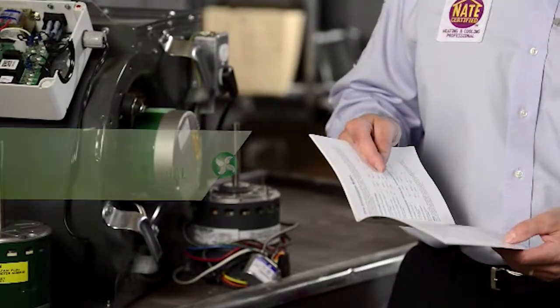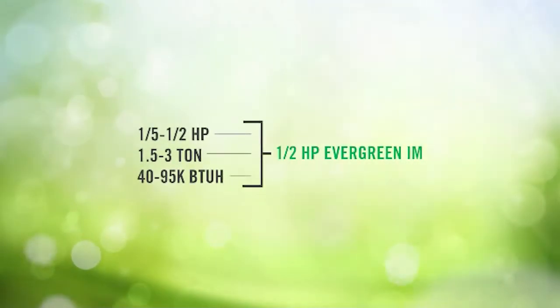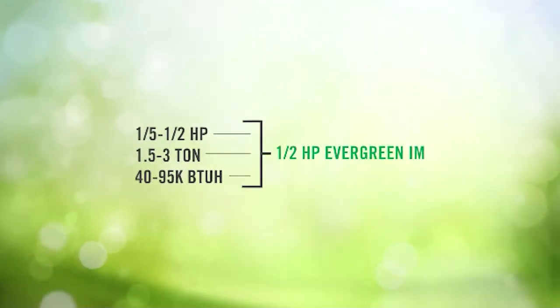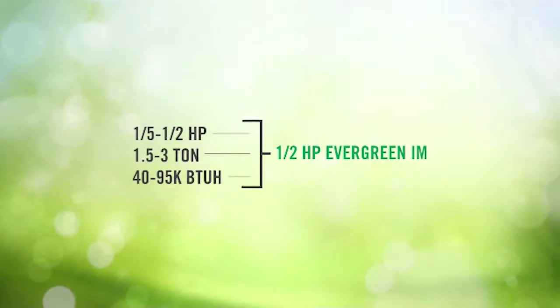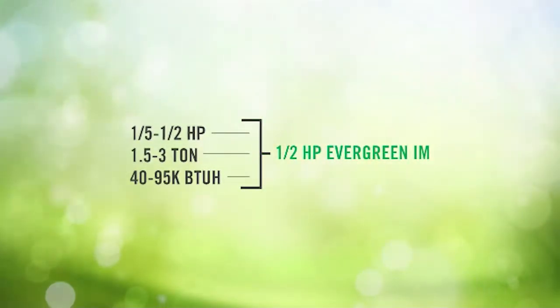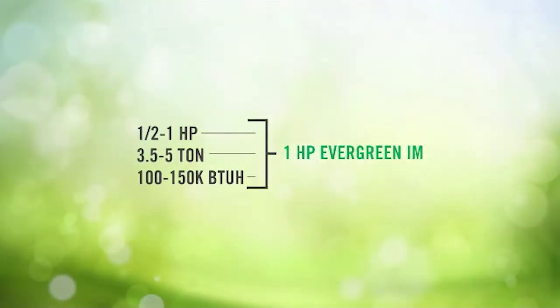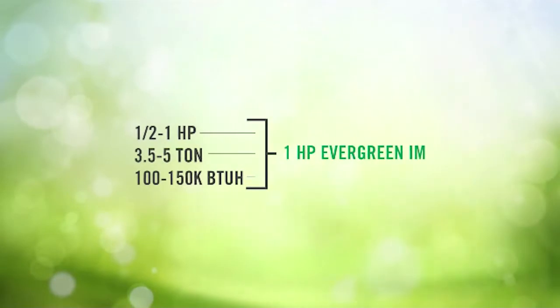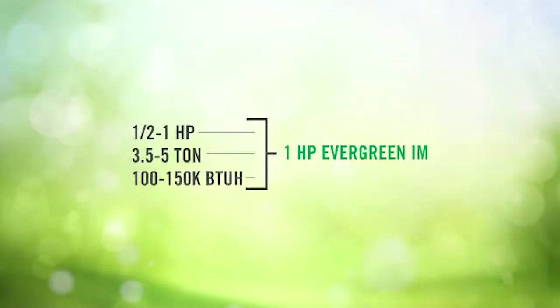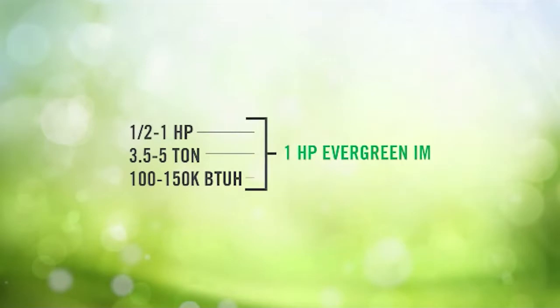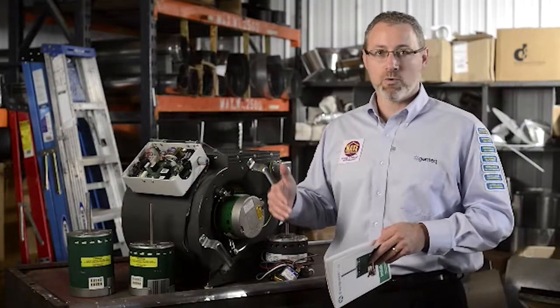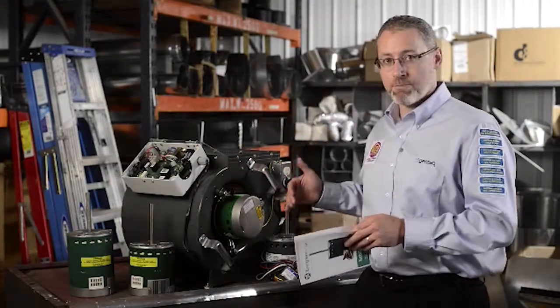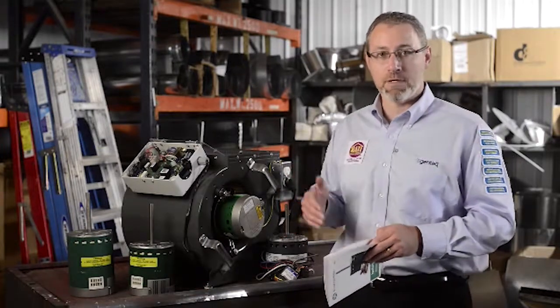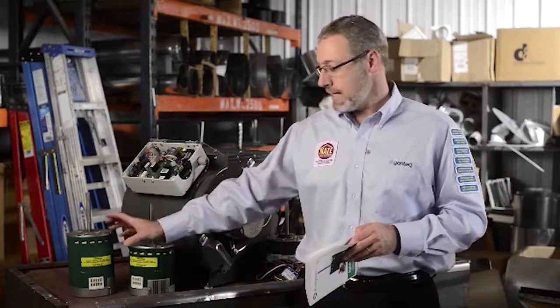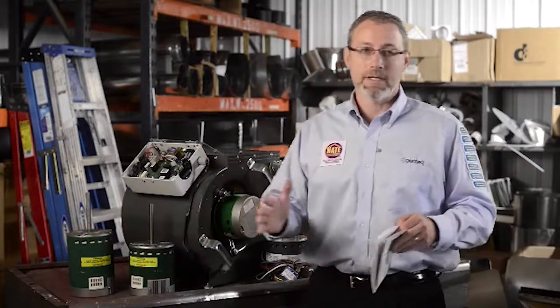The selection guide is going to tell you that if you have a 1.5 to 3 ton air conditioner and or a 40,000 to 95,000 BTU furnace, you would select the 1/2 horsepower motor. It's going to go on to say if you have a 3.5 to 5 ton air conditioner, or if you have a 100,000 to 150,000 BTU furnace, you would use the 1 horsepower motor. Selecting the correct motor for your 1/2 horsepower needs makes sure that you don't spend more money than you need to on the larger motor, and that you're not trying to put a larger motor in a smaller application.